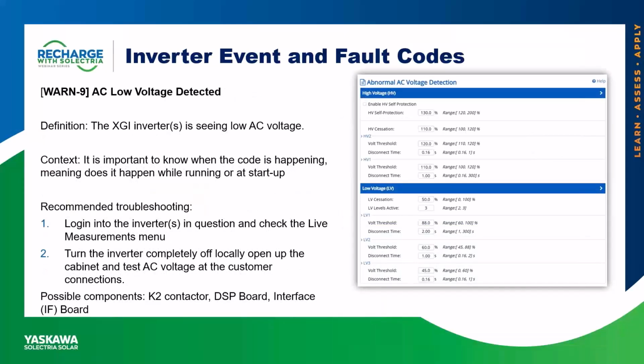Next code here is warn 9, AC low voltage detected. Essentially, the inverter is seeing low AC voltage. Similar to a warn 2, this is one of the codes you might see when you first turn the inverter on for the first time, especially during the commissioning process. But again, at that point, the code could possibly be a byproduct of the situation, as typically during the commissioning process, there is no AC voltage present at the inverter. This is why I mentioned on this slide it is important to know when the code is happening, meaning does it happen while running or at startup.